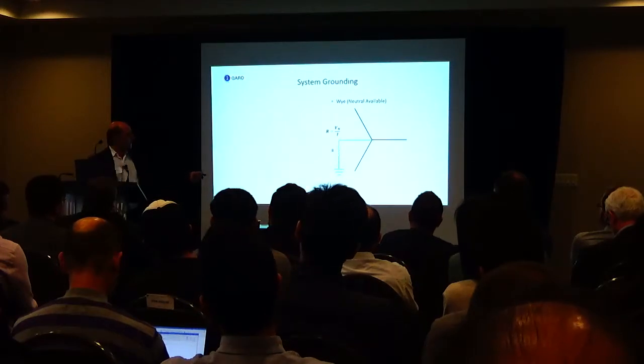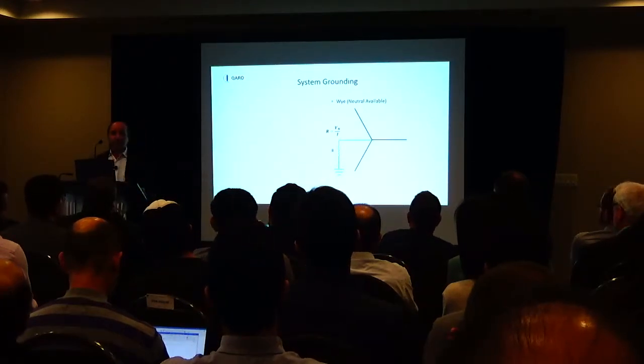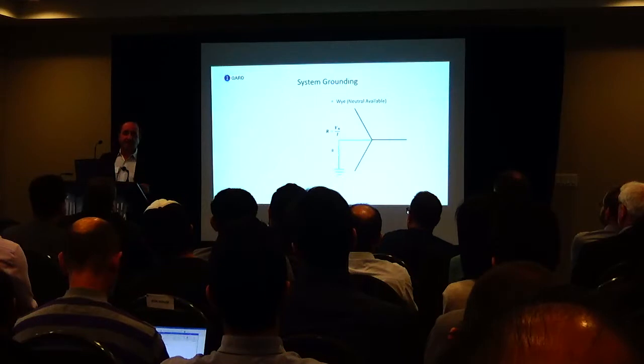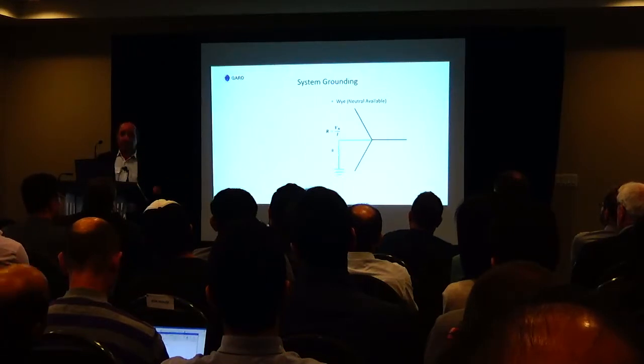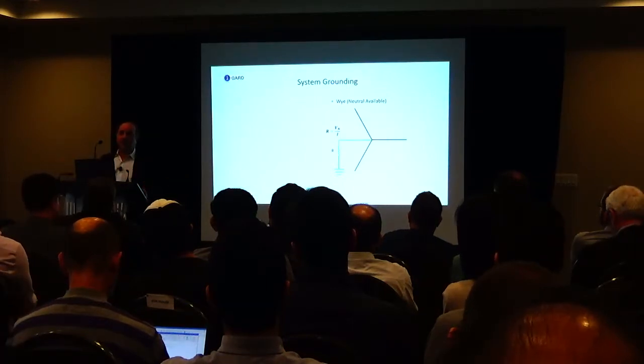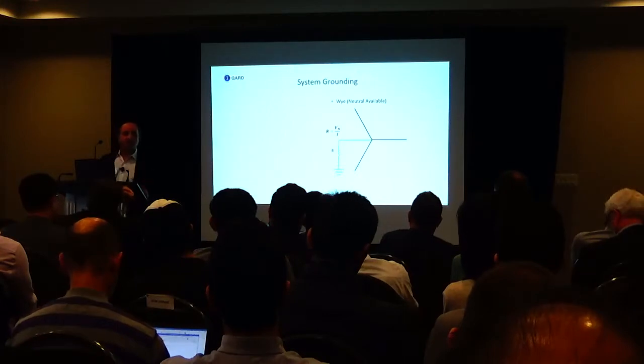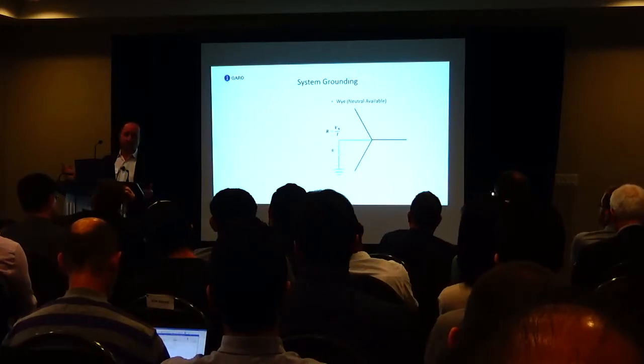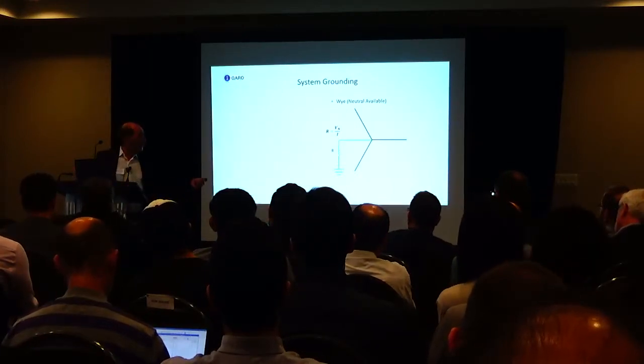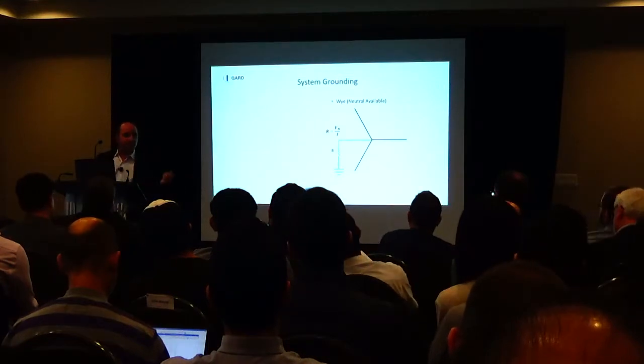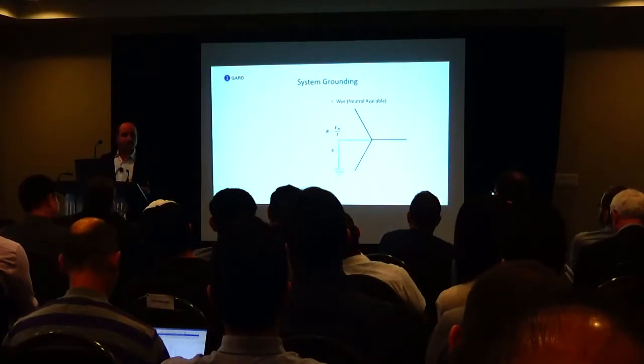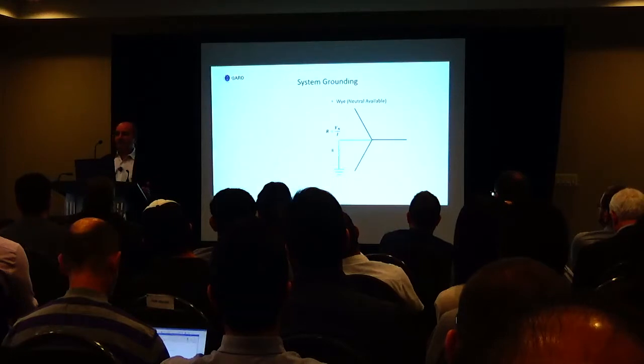So when the neutral is available, we can just put a resistor on it. It's easy to calculate the size of the resistor. You need what you want to limit the fault current to, and the line to neutral voltage. So if you had a 4160 volt generator, you want to limit the fault current to 400 amps. 4160 divided by root 3 gives you the neutral voltage, 2400 volts, 400 amps, 6 ohms.